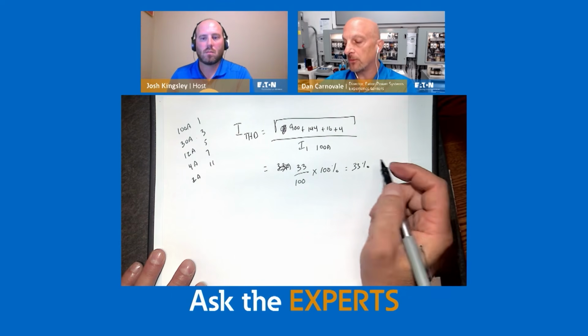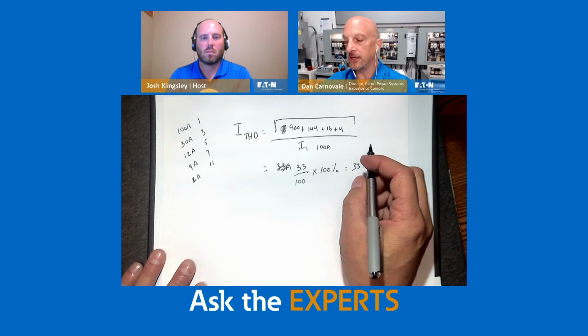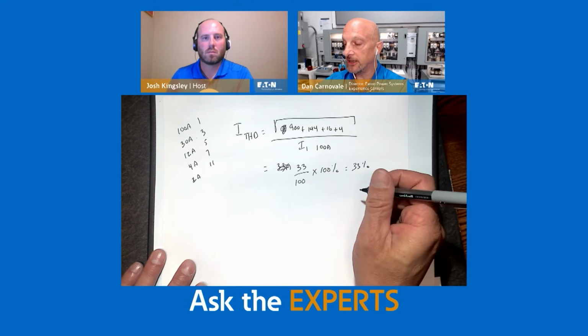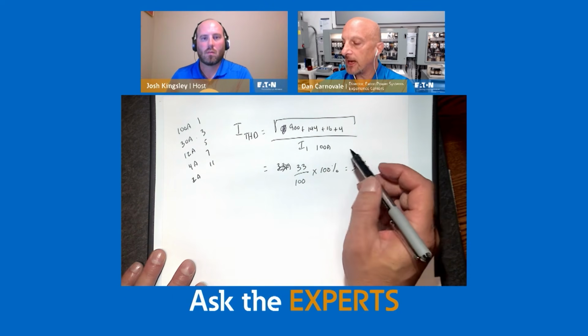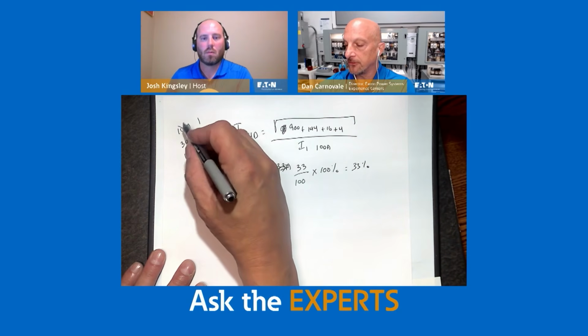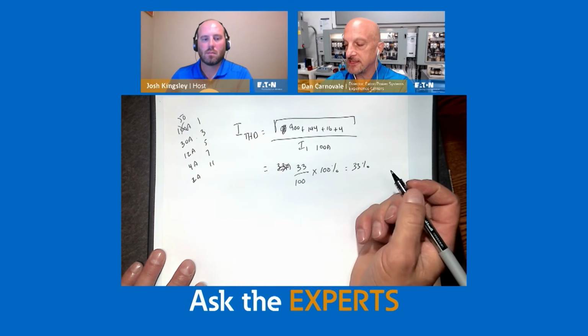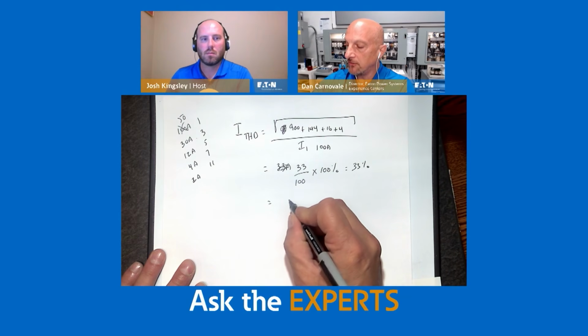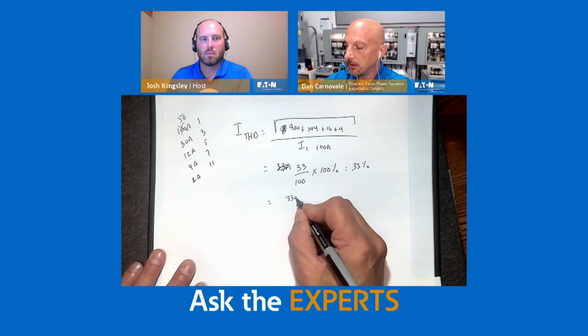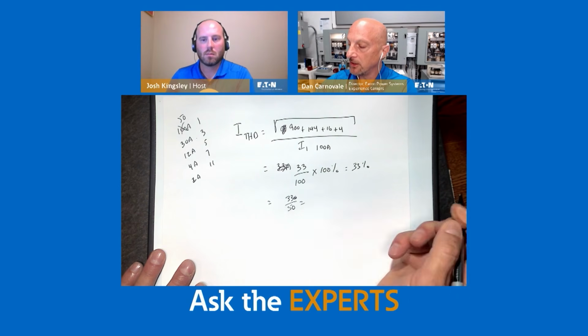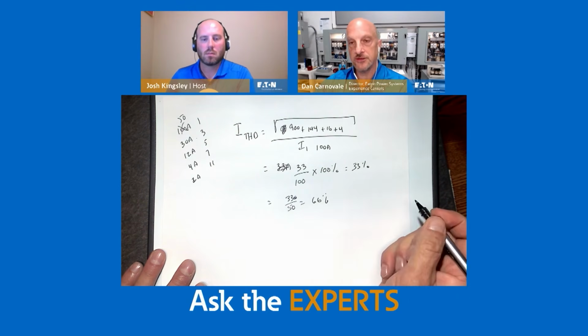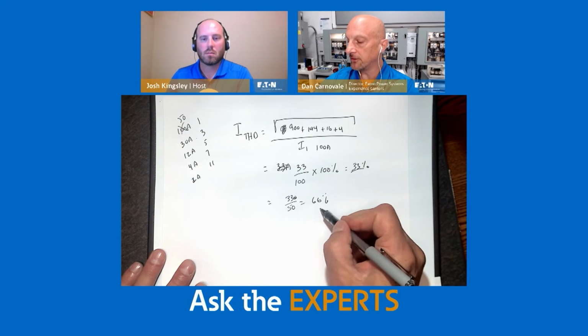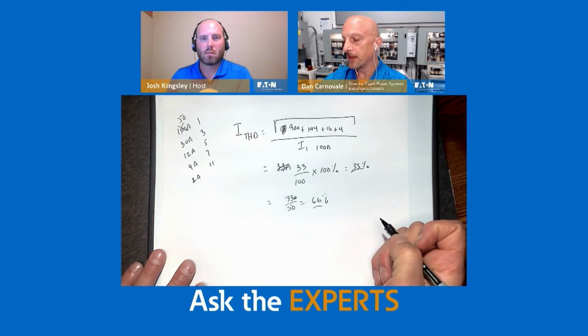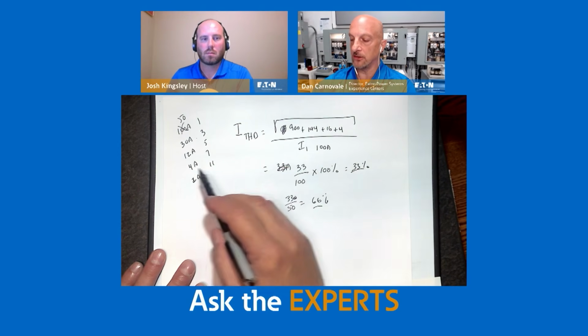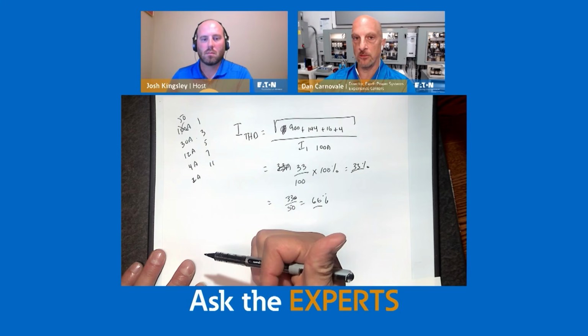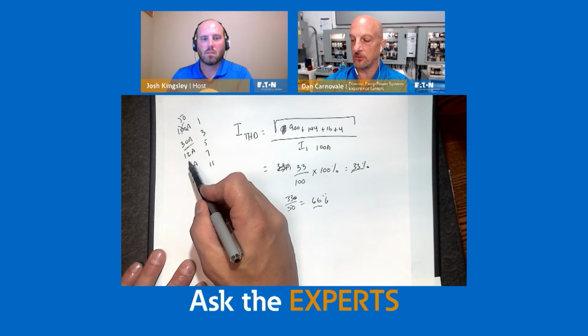Now, remember earlier I mentioned that if you were running overnight with a light load condition, you might have a higher percent THD. Let's say the fundamental overnight goes to 50 amps, but mostly the rest stays the same. So 33 divided by 50, and now guess what my THD is? 66%. Is this number worse than that number? This is where THD can get you in trouble. It's really the same. The same amount of harmonic current is flowing through my power system and heating up my equipment in actual amps, and actual amps are the most important part.